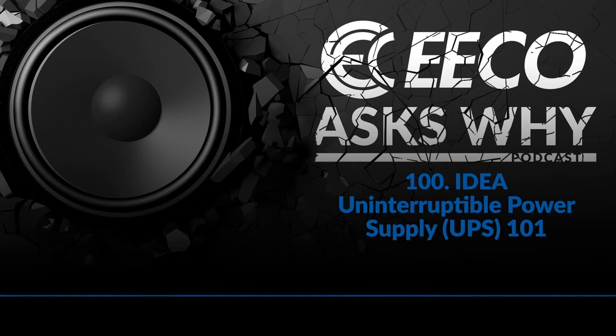That brings up a good point. A lot of times people think, hey, I've got a UPS, I don't need a generator. Or, hey, I've got a generator, I don't need a UPS. When in reality, they're going to work in tandem together. Things like your motors, that's a great thing to put on a generator. But a lot of times you're going to have a whole building or whole facility generator, so you can use the UPS in between that generator and your downstream processor devices. The UPS can provide that ride-through on a lot of your devices until that generator gets up to speed and synced in.